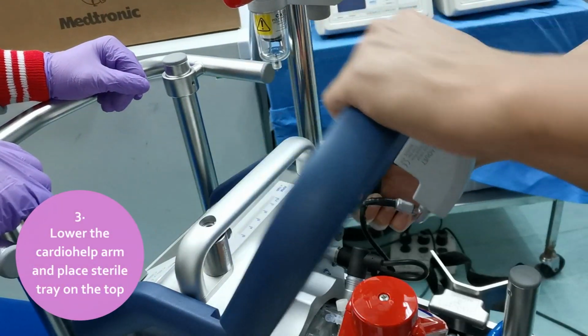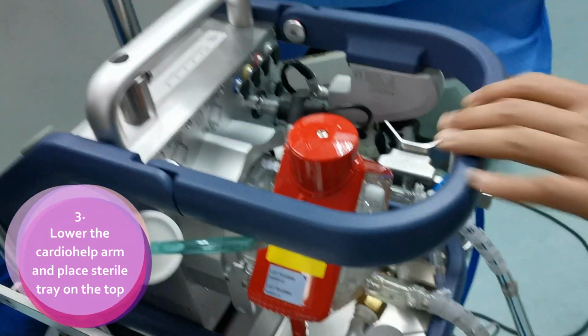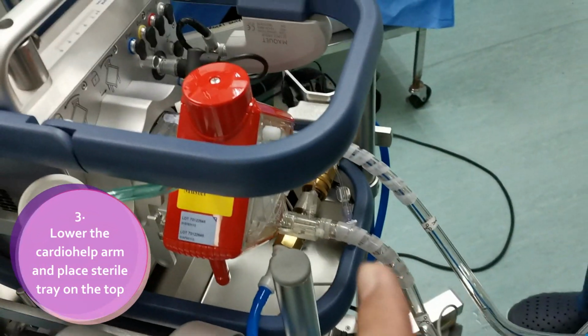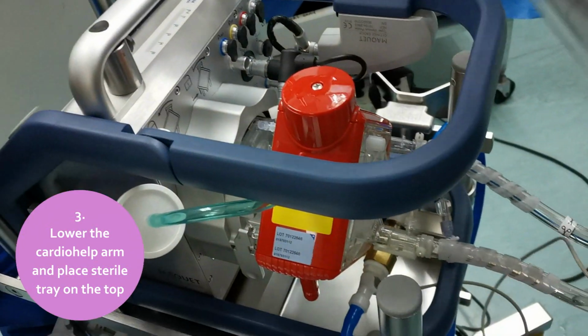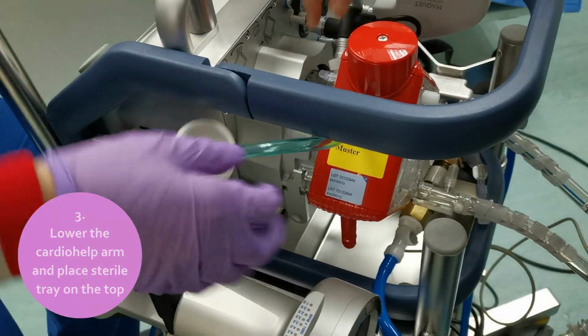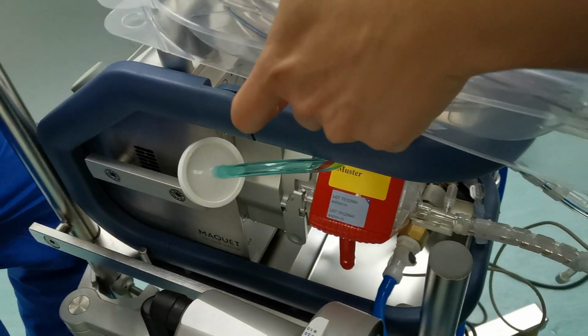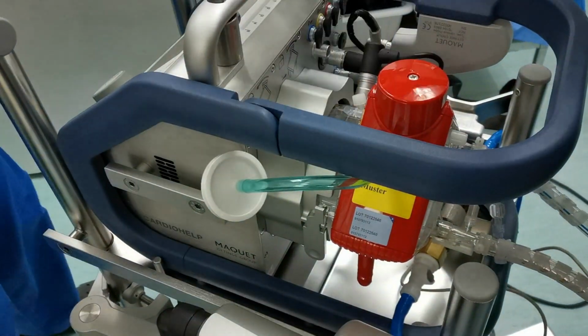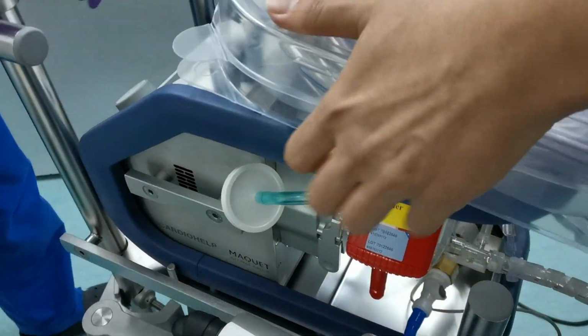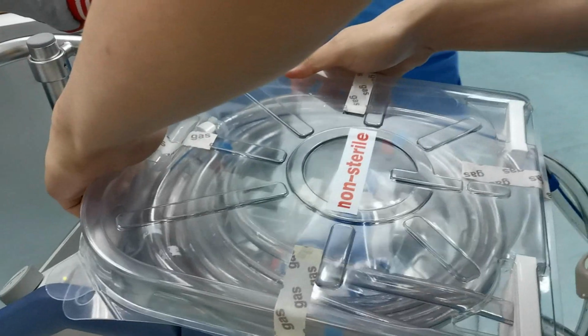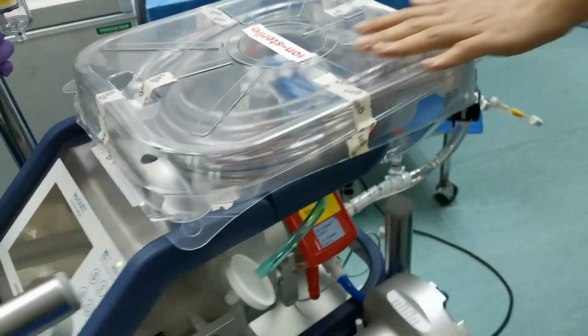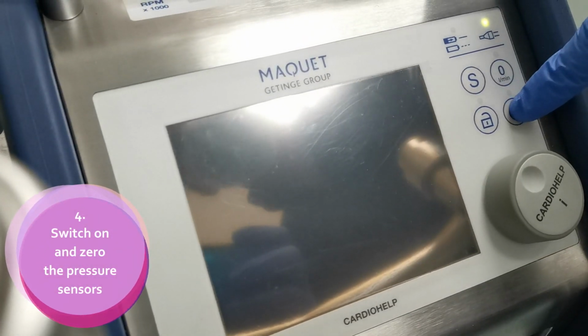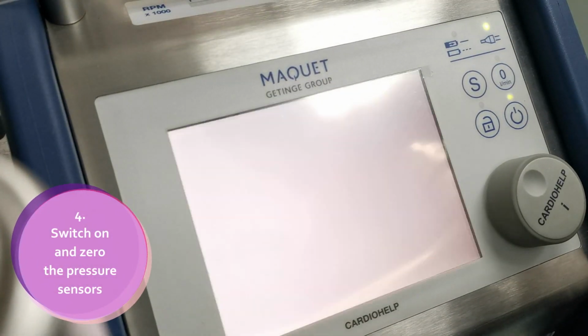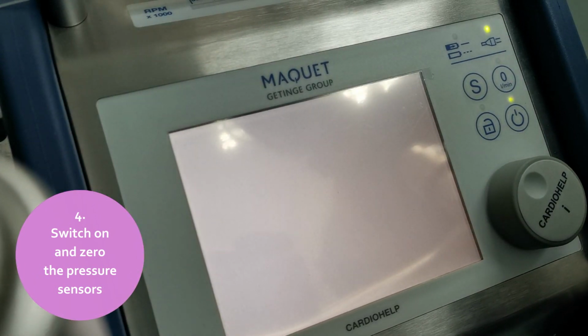After that, lower the CARDIOHELP arm by pressing the 1 button on the right side and securely place the sterile tray on the top of the module. Contents of the tray must remain sterile throughout the priming procedure. After installing the HLS module, probe, and sensors, the main console can now be switched on by pressing the universal power button.